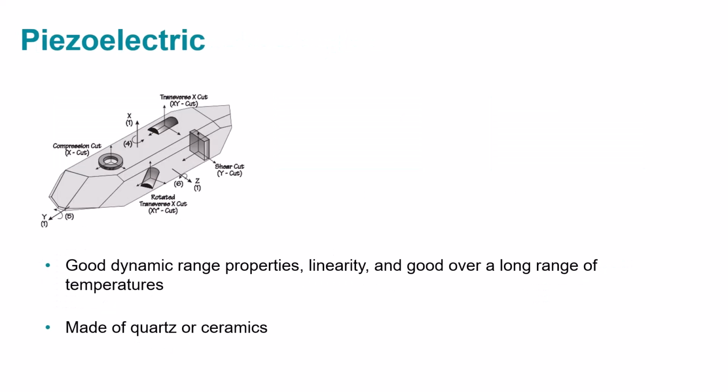So piezoelectric is a really cool kind of phenomenon. Piezo comes from the Greek word for pressure, to squeeze. And essentially what happens is inside an accelerometer, there is a tiny little crystal. It can be made of a couple different things. It can be made of quartz, it can be made of ceramic. But when you squeeze this crystal, it's outputting a voltage proportional to how much it was squeezed or deformed.